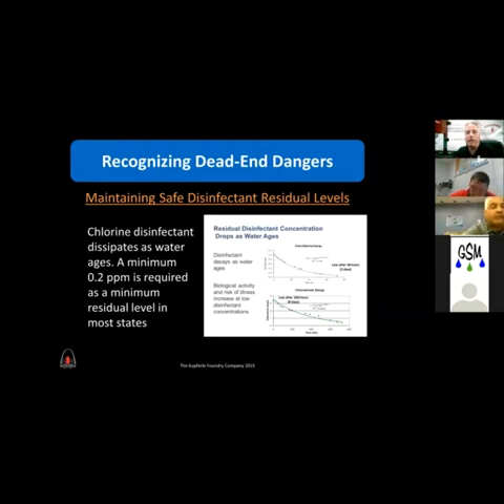Chloramines is about half that decay rate. So if you're using chloramines or a combined chlorine, usually it stays in the water longer. And a lot of the bigger cities and the rural districts will use chloramines to keep chlorine in the water longer. But a good yardstick for water quality, especially if you're doing free chlorine, is about a week, 4 days to 7 days. If my water is less than a week old on a dead end, I'm probably okay.